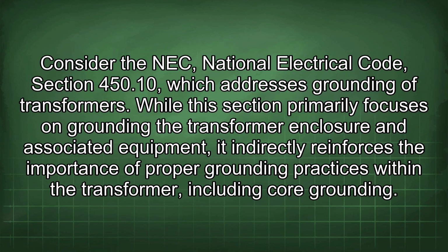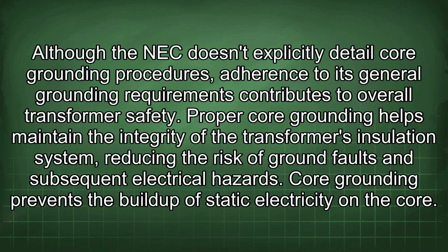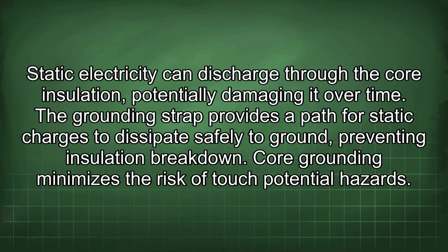Consider the NEC, National Electrical Code, Section 450.10, which addresses grounding of transformers. While this section primarily focuses on grounding the transformer enclosure and associated equipment, it indirectly reinforces the importance of proper grounding practices within the transformer, including core grounding. Although the NEC doesn't explicitly detail core grounding procedures, adherence to its general grounding requirements contributes to overall transformer safety. Proper core grounding helps maintain the integrity of the transformer's insulation system, reducing the risk of ground faults and subsequent electrical hazards. Core grounding prevents the buildup of static electricity on the core. Static electricity can discharge through the core insulation, potentially damaging it over time. The grounding strap provides a path for static charges to dissipate safely to ground, preventing insulation breakdown.